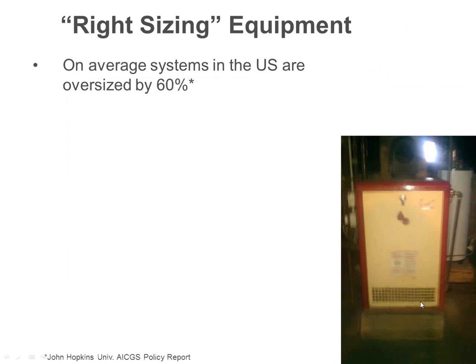Okay, one thing that we always talk about is called right sizing. I've been doing this for 25 years. I have not, to this day, found a boiler that was undersized on a heating system. Domestic water systems, snowmelt systems, maybe, but on a heating system, I have not found one to date that was undersized. Most of them, like we say here, are oversized by an average of 60%. Okay? Think about it. A boiler is designed to work on the coldest day. The kicker is that's less than 1% of the heating year.